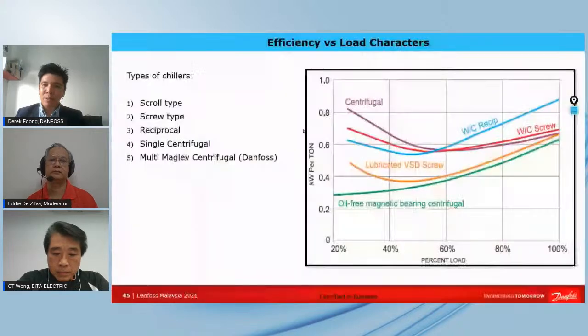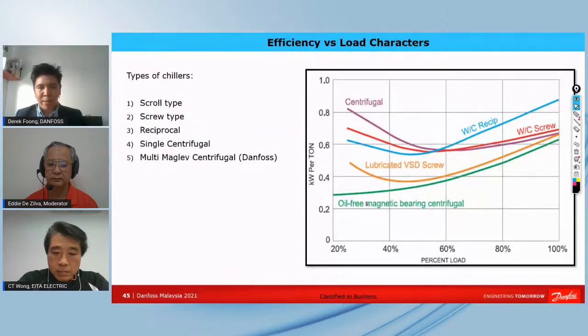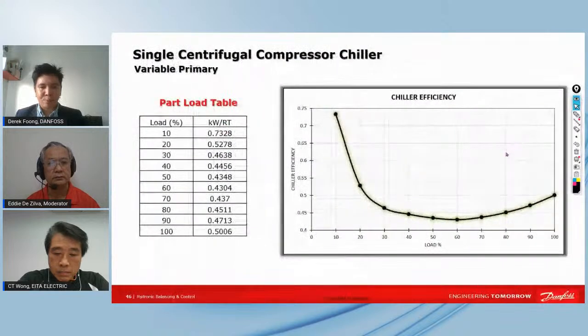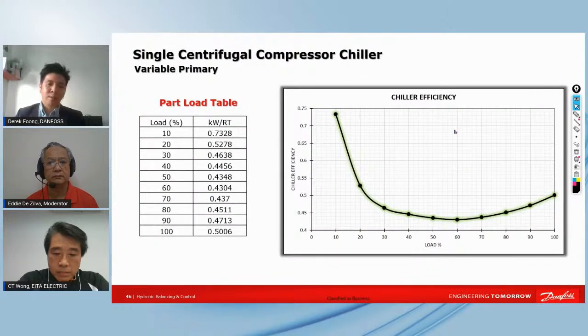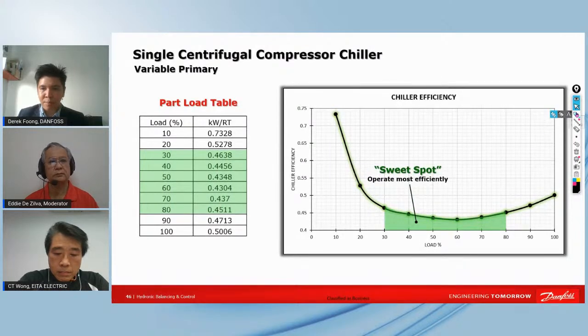So when we look at the variable speed chillers, the sweet spots are always defined during part load, and usually it's like a U curve. If we look at the green color curve, that is where we have magnetic levitation compressors that operate more efficiently than other compressors. So with this newest technology, usually when we work closely with end users or designers, they would send us a table, and we would plot out this area where we would simulate.